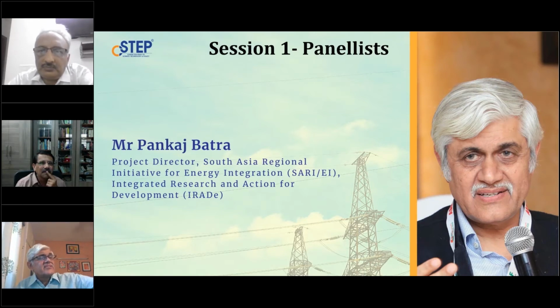Also, since you're talking about pump storage plants, I'd like to point out that the new type of pump storage plants coming up, like the one coming up in Tehri, is a variable speed machine, which is more efficient than the constant speed machine used up till now. It also helps manage frequency control much better, because you can pump water to different extents - it's not a constant pump, constant speed pump that pumps out at a constant rate.